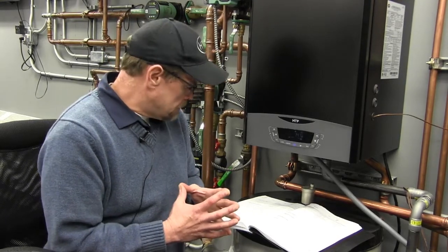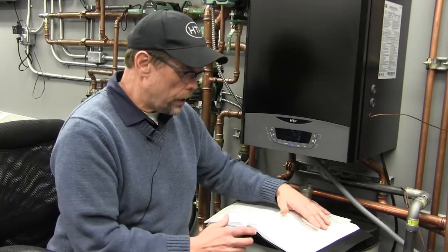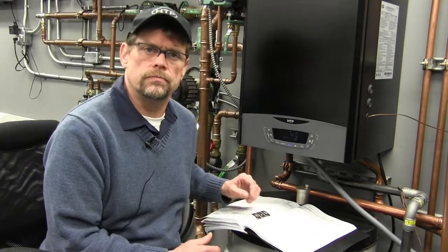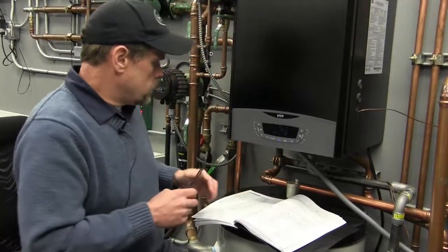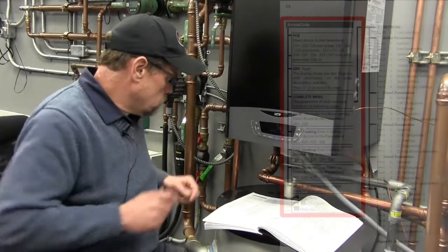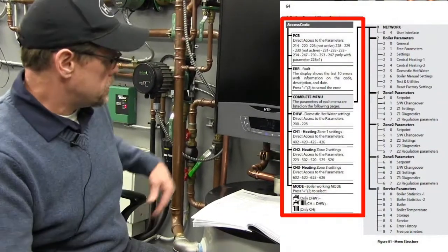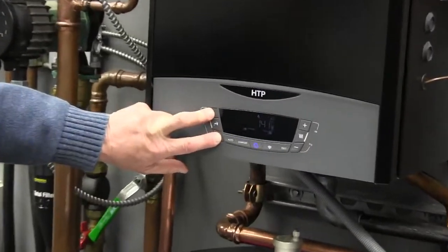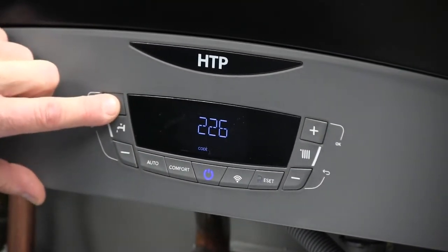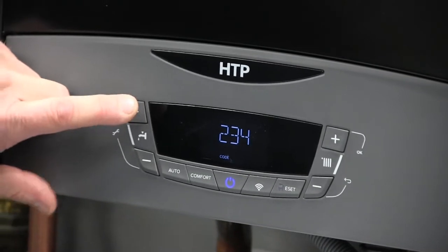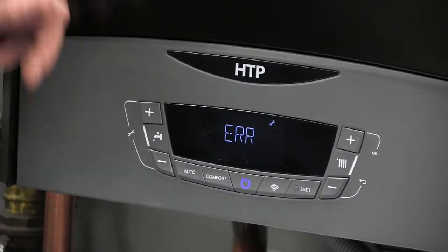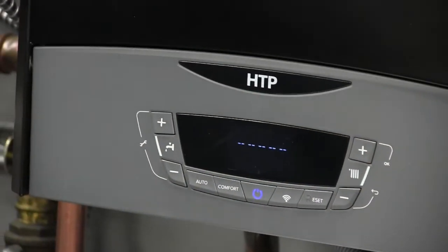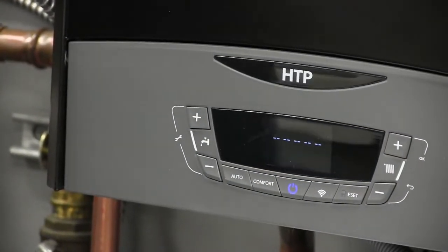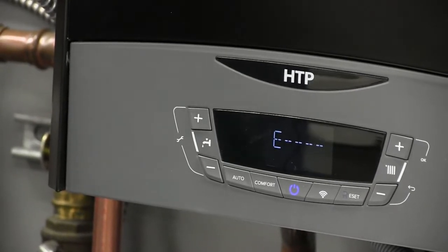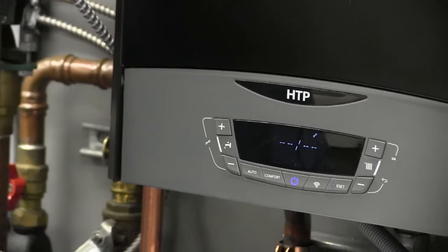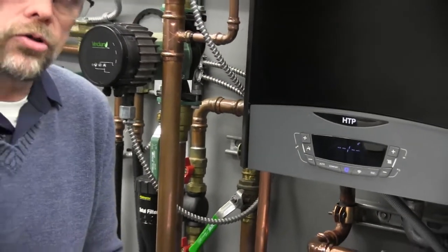So let's dig into this a little bit further. I think what we're going to go into next is we'll take a look at the error codes. To access the error codes, again, we can look here on page 64 through our quick access. So we're going to hit the plus and minus on the service wrench. Enter 234 for our access code. Hit OK, and then move to error, and we hit OK. Now, when we wait a minute, it will tell us what the latest fault was. So this was the one that just happened most recently.